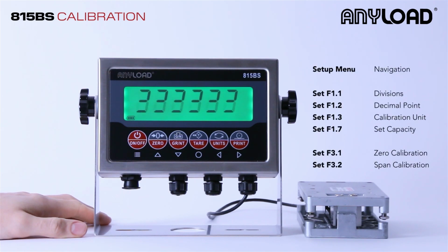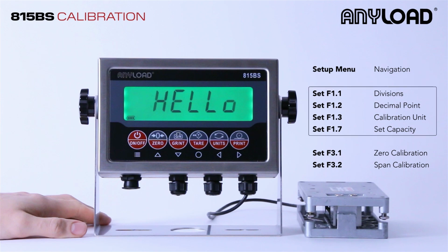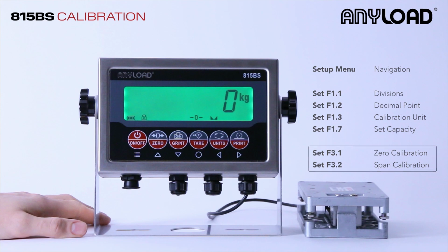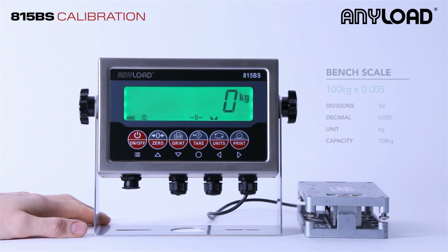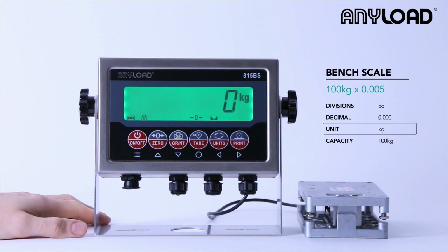Today we're going to be talking about our setup menu and its navigation, setting our F1 settings, which include divisions, decimal point, calibration unit, and setting max capacity, and our F3 settings, which include zero calibration and span calibration. We're going to be setting this up as if it was a bench scale. So we'll set our divisions to 5, 3 decimal places, our units to kg, and our max capacity will be 100 kg.